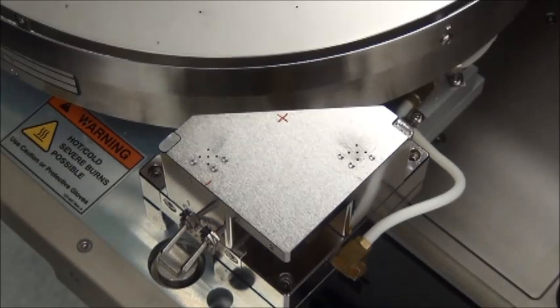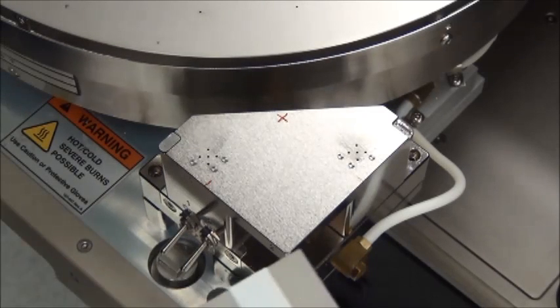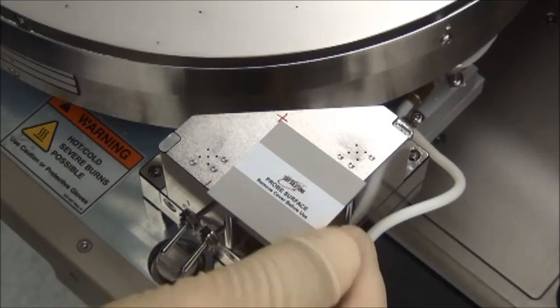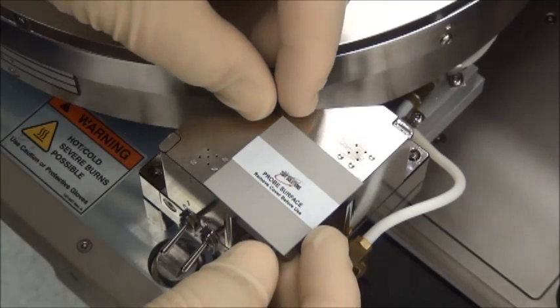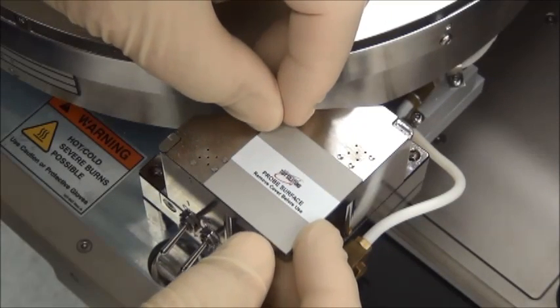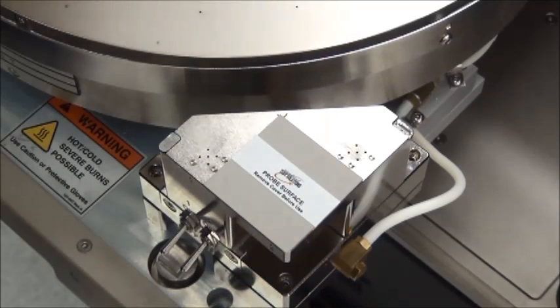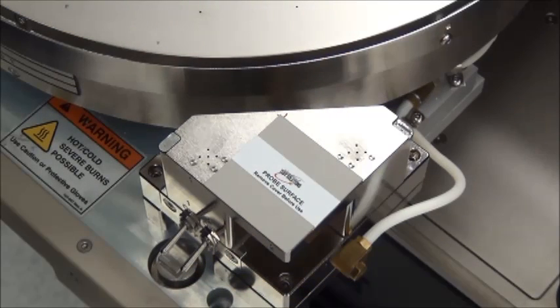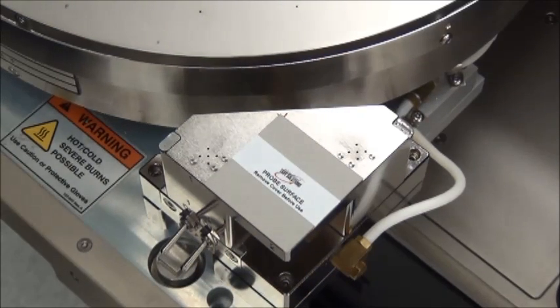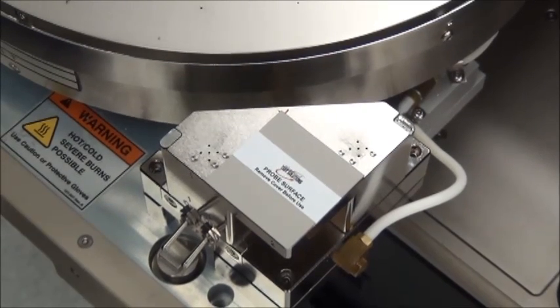Before installing the pad, perform a dry fit check to make sure the shape and size of the pad matches the available aux chuck real estate. As mentioned before, our cleaning pad is designed by International Test Solutions to precisely fit our chuck area, so there is no cutting involved which makes installation a little easier.